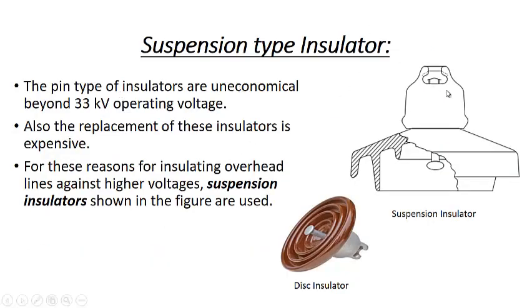So usually we have, let us say we have only one. Here we are connecting it to the cross arm, and here we are connecting the conductor at this point. One more thing, they are usually designed for 11 kV, one unit, and if we have to use it for 33 kV, we have to use 3 units. And if one disk is damaged, we can replace only the 11 kV disk instead of the whole unit.